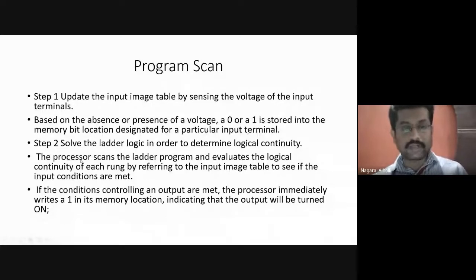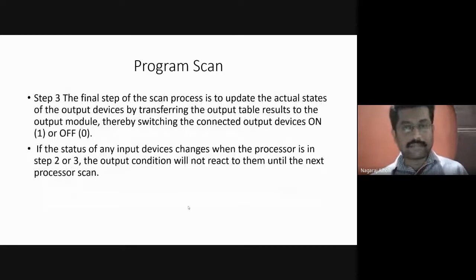Solve the ladder logic, that is, it executes the ladder logic instructions based on the logical continuity. If the conditions controlling an output are met, the processor immediately writes a 1 in the memory location, indicating that the output should be in on state. The last step of the scanning process is to update the actual states, that is, it updates the output field devices.